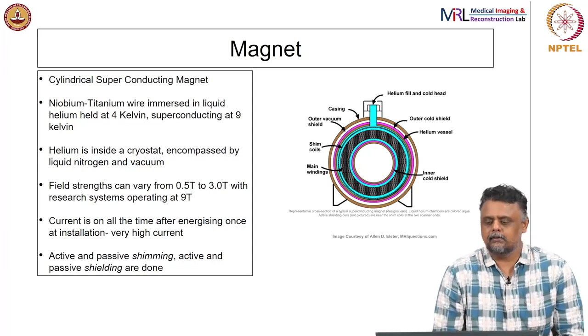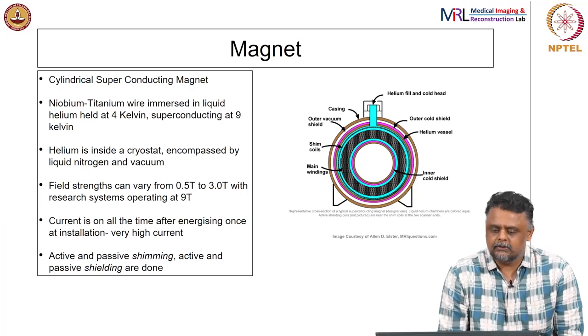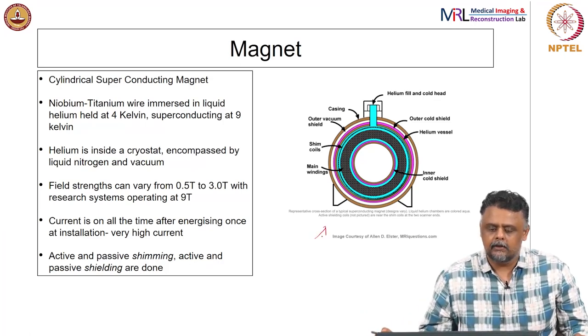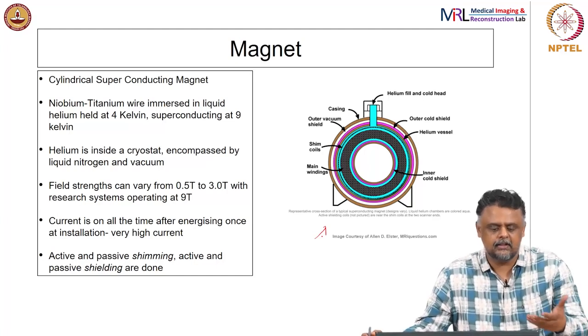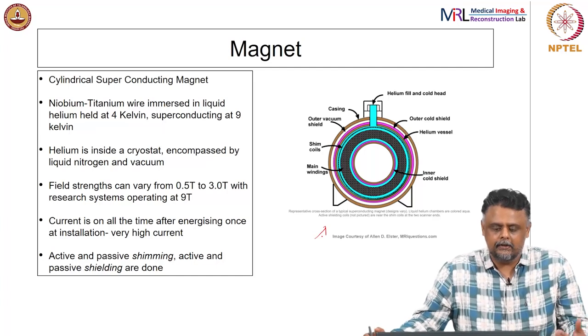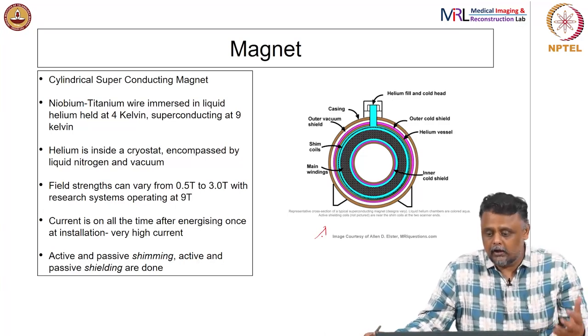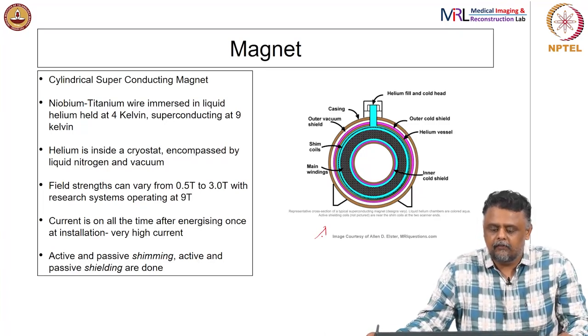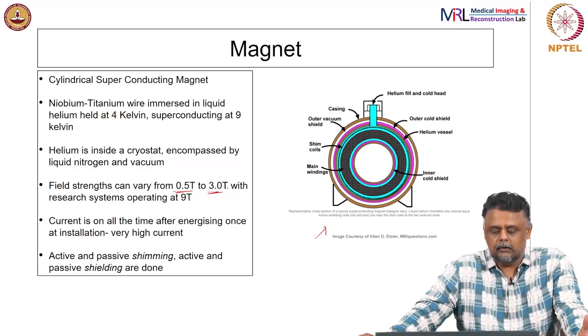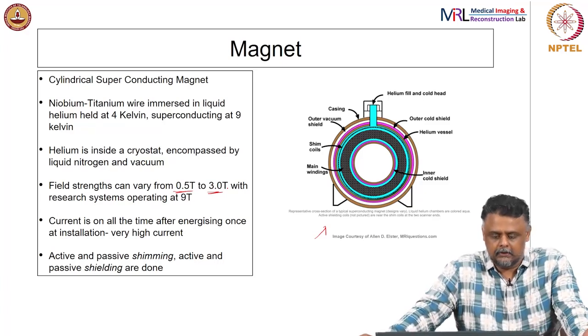As far as the magnet is concerned, it is the main component and also the most expensive. It is typically a cylindrical superconducting magnet. A cross-section is shown in the figure. It has a superconducting wire — in this case niobium titanium wire — immersed in liquid helium held at 4 Kelvin, though that wire is superconducting at 9 Kelvin. The helium is inside a cryostat encompassed by a vacuum and liquid nitrogen. Field strengths vary from about 0.5 tesla to 3 tesla, though 9 tesla magnets also exist for small animal biomedical imaging and research.